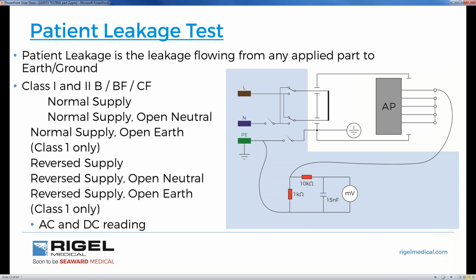as if it's the definition of a medical device for its intended purpose of use. That we are measuring the current that flows from a single applied part through the body model. Remember, the blue here is internal to the Rigel. Measured through our 1K body model back to protective earth. So we are measuring any stray capacitance, any current that could be passing through any stray capacitance or dielectric resistance from your applied part back to protective earth.